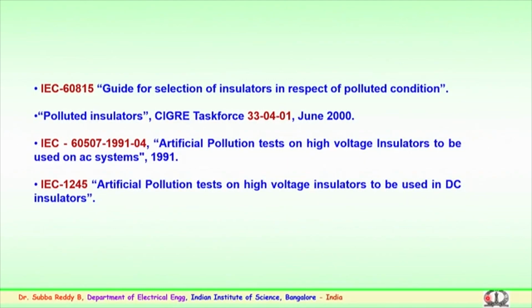We have already discussed that there is a difference between AC and DC insulators. DC insulators require different arrangements or experimentation, wherein the creepage is very high, and the material used for DC is slightly different from that of AC insulators, as we have discussed. The alumina content in the material should be higher. The methods adopted are similar in nature to the AC pollution tests, but with modifications. These are clearly mentioned in the standard 1245.